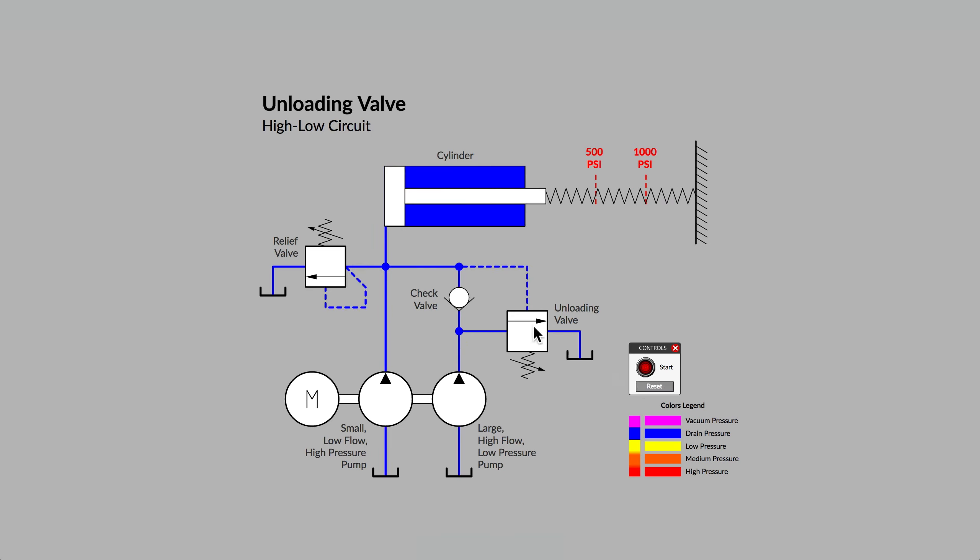The symbol for an unloading valve is quite similar to the symbol for a pressure relief valve. They are both normally blocking or normally closed off valves. Springs are used to keep the valves in their closed position. They are both waiting for a high enough pressure value on the dashed pilot line to cause them to open and pass flow.